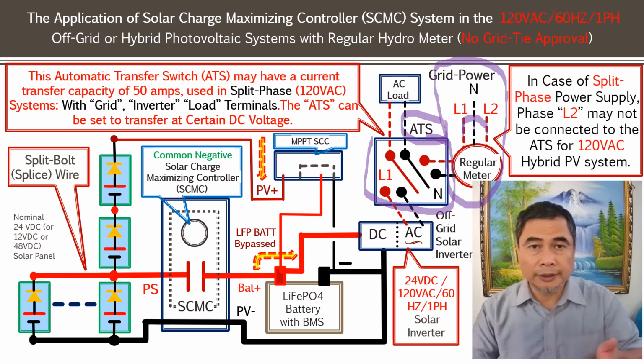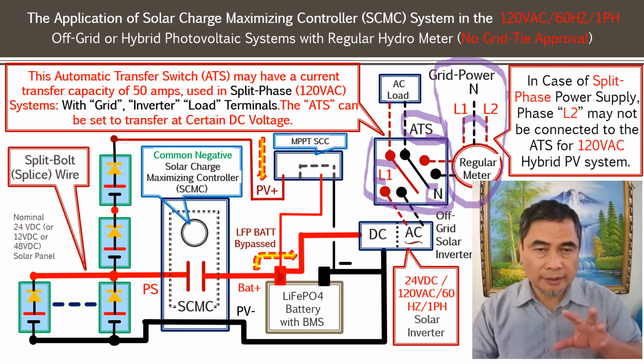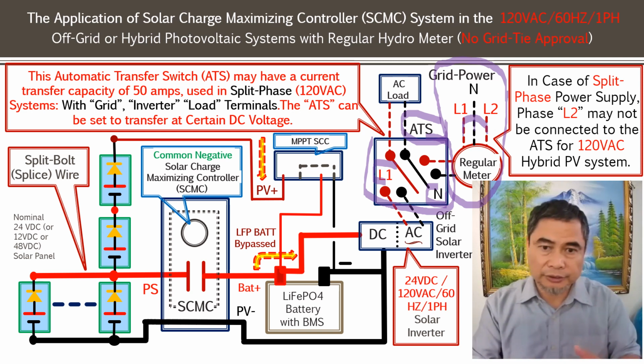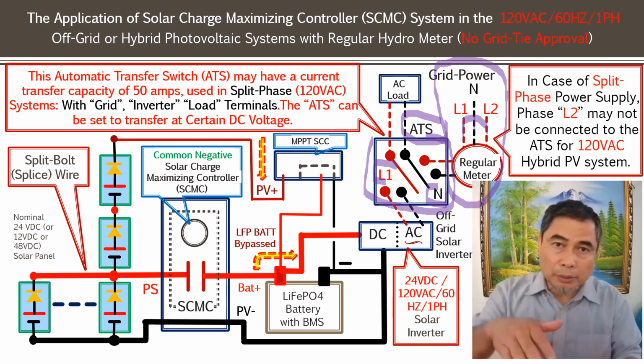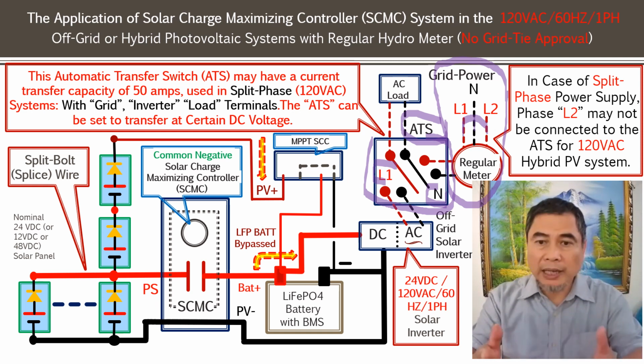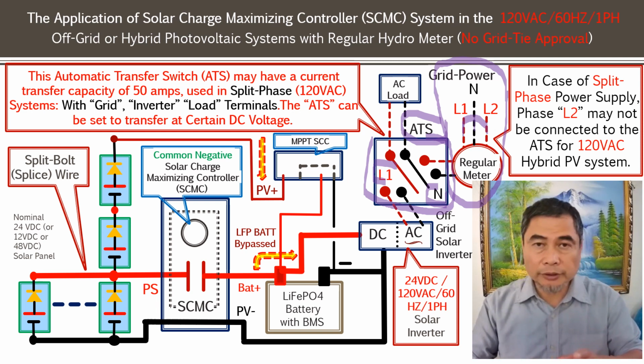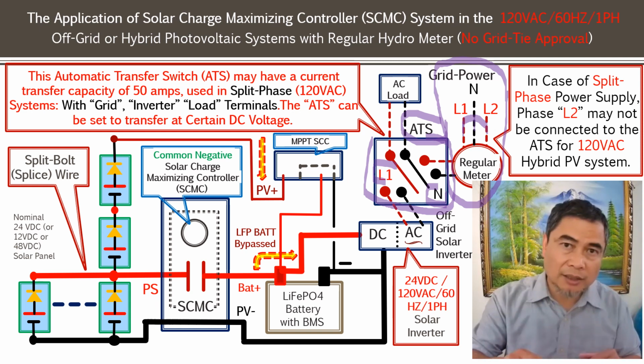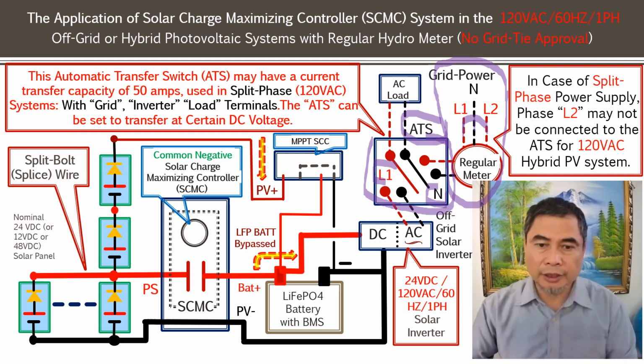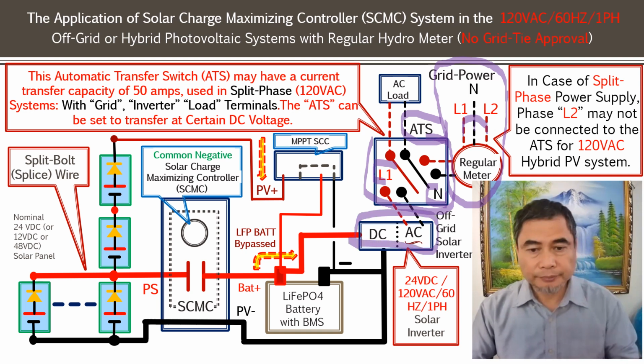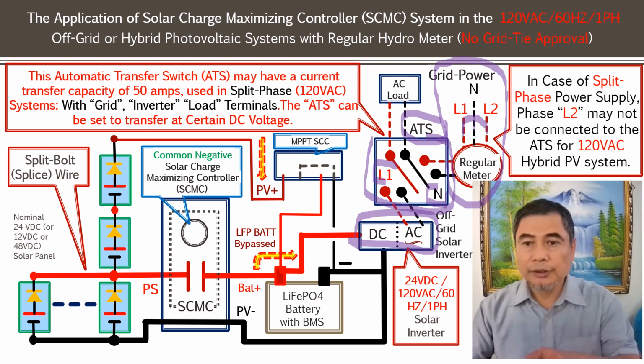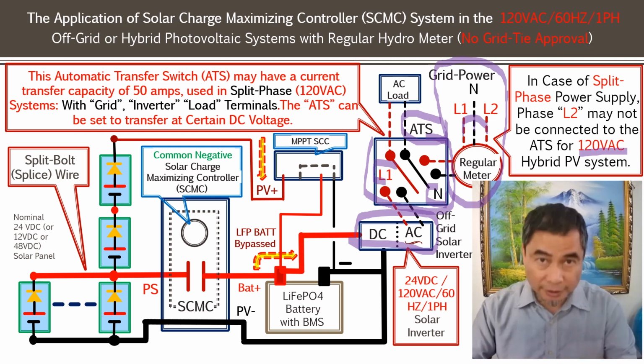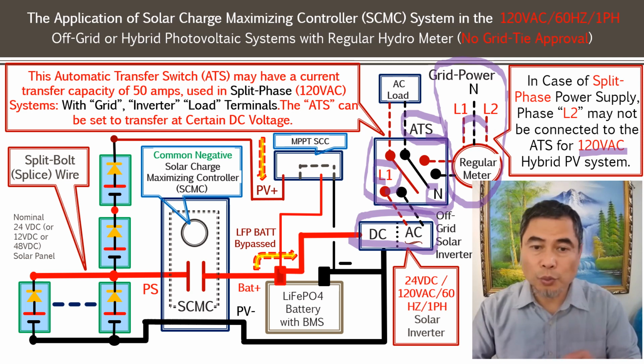You can use it for a 120 system, you can use it for a 220 system, but it's only a 1-line voltage, 1 neutral. Actually, the relay inside is powered by that line voltage. Without any power supply, it automatically falls back to the grid. That is how the automatic transfer switch has been designed. With no power, or when the DC power is very low, the system automatically falls back to the grid power. As long as the DC voltage rises above the setting mark, say 26.5, the relay will work and then switch the load to the off-grid inverter here. That off-grid inverter makes sure it's 120 VAC, 60 Hertz to match what you have. You notice that only 1 line is being connected to it.